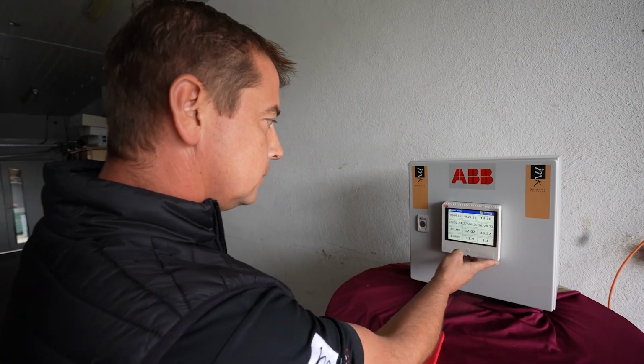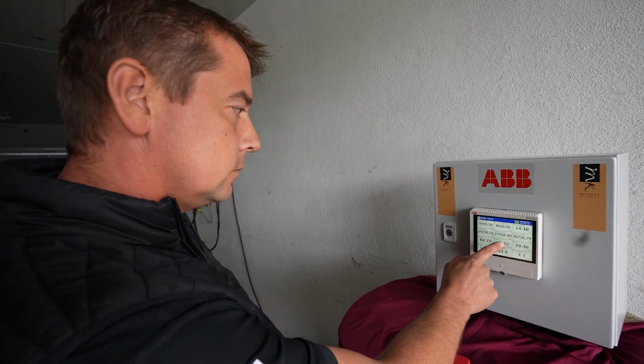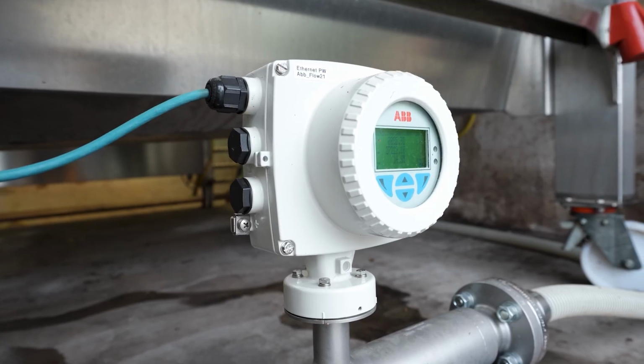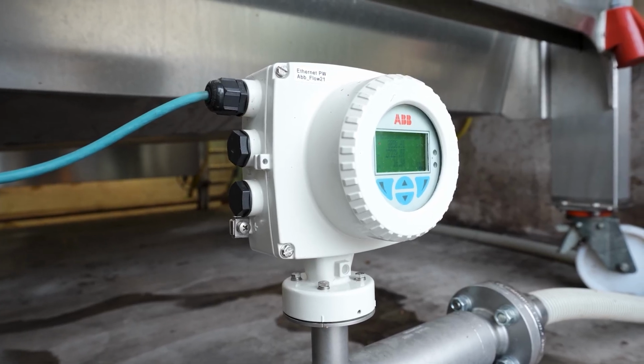But there was only one of these values you had to decide to read. With Ethernet now, the customer has access to all the values. This saves a lot of measurements because more is integrated in the same device. And then you can extend the calibration cycles, which is a direct saving in money, because calibration typically means getting out the instrument and stopping the process.